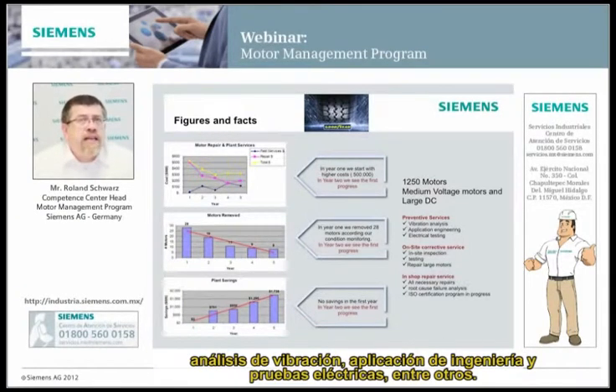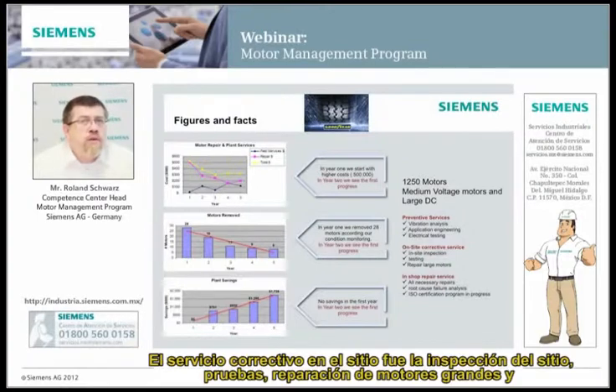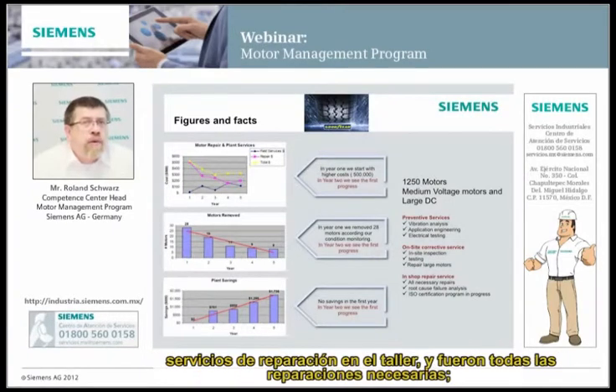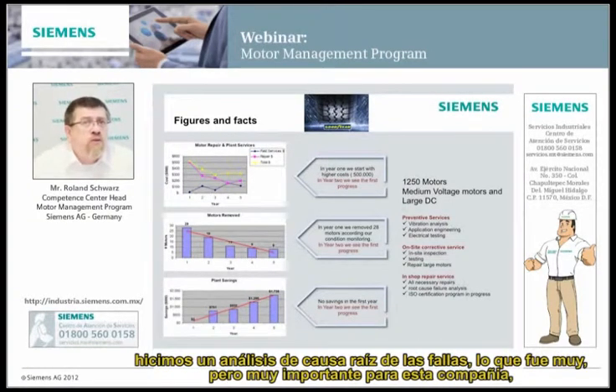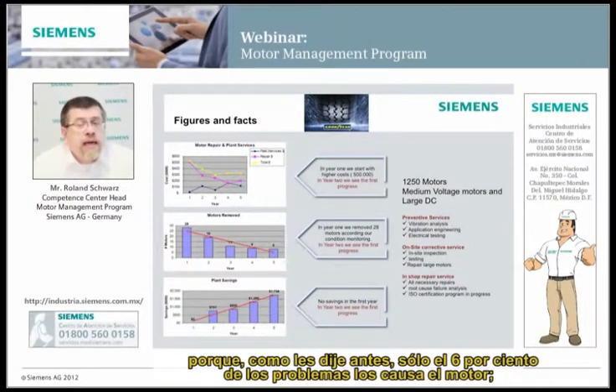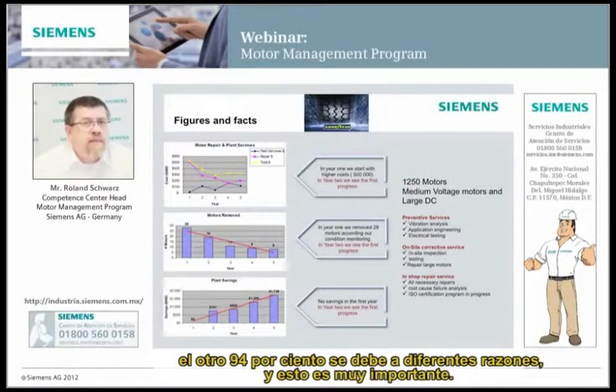Vibration analysis, application engineering, electrical testing. The on-site corrective service was in-site inspection, testing, and repair of large motors, and the in-shop repair service covered all necessary repairs that came out. Root cause failure analysis was very important for this company, because as I told you before, only 6% of problems are the motor itself - 94% are different reasons. That's very important for us to have.